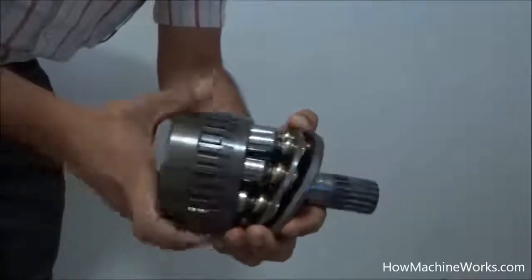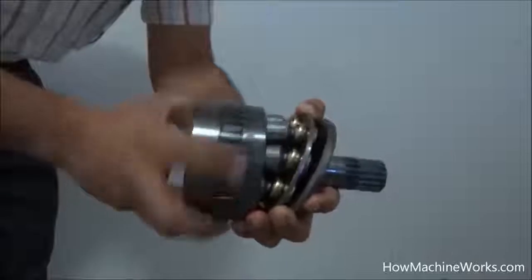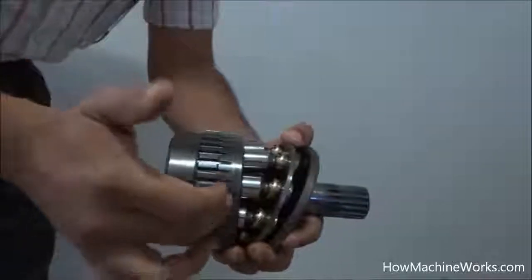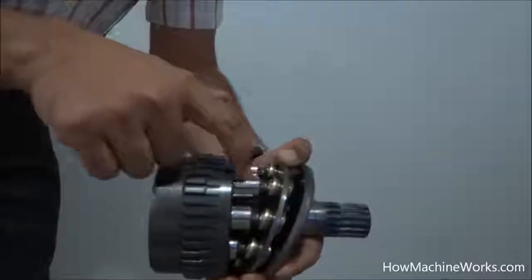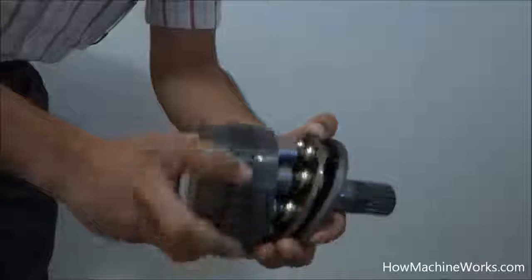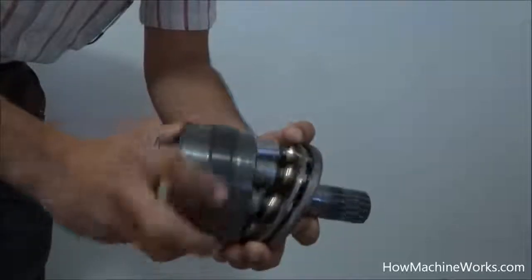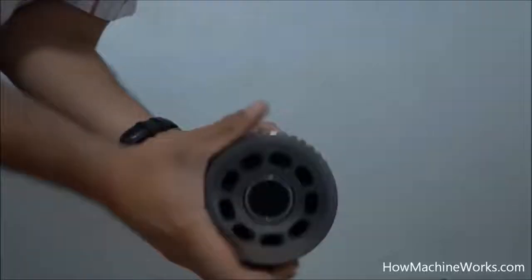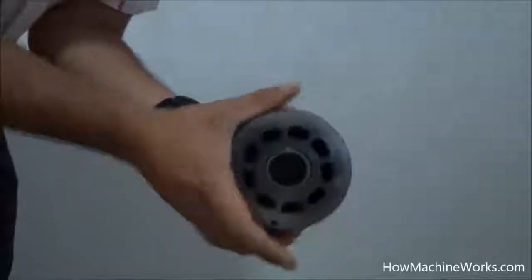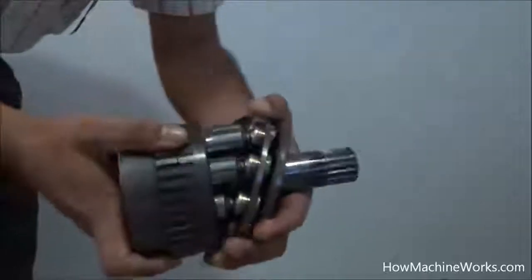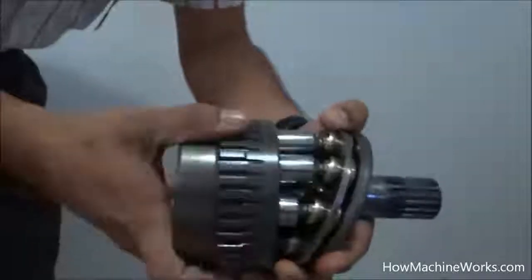So here you can see how the pistons actually move as the cylinder rotates. Both the drive shaft and the cylinder are rotating. At the bottom, the piston is moving back, which is creating a suction, and moving towards the top, the piston actually reaches the maximum suction, and as it rotates to the other side downwards, the delivery is happening. You can see the piston movement inside the pots of the cylinder very clearly over there. Have a closer look, and that's how it exactly works.